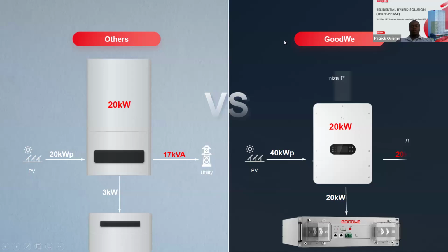The next application is the oversizing of your system. Now, if you look at the other brands in the market, for example, if you're taking a 20 kilowatt hybrid system of another brand, you can only connect a 20 kilowatt PV system to it. And it does not just end there. The output capability of such a brand is a bit limited, because the other brands usually split the power rating of the inverter on the AC side. So you get around 17 on the AC, then 3 on the DC to give you a total output of 20. So you get a 20 kilowatt inverter giving you a 20 kilowatt output.